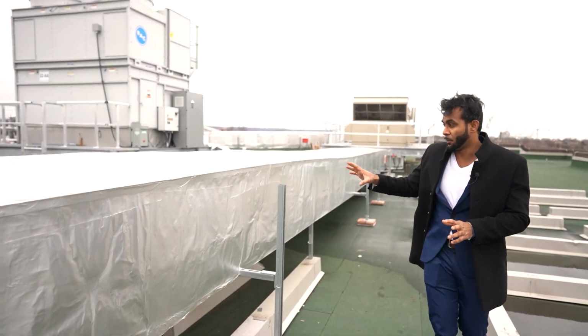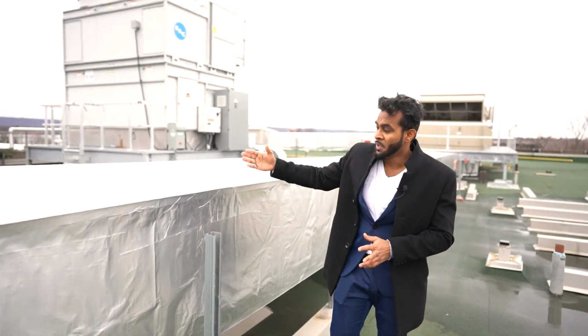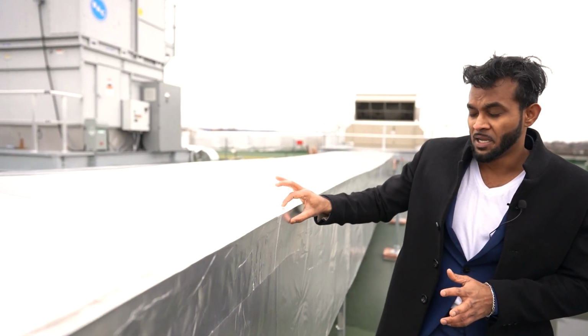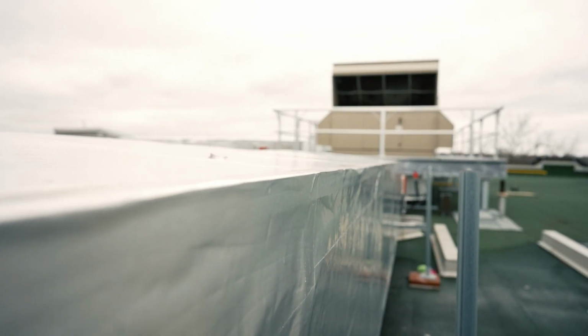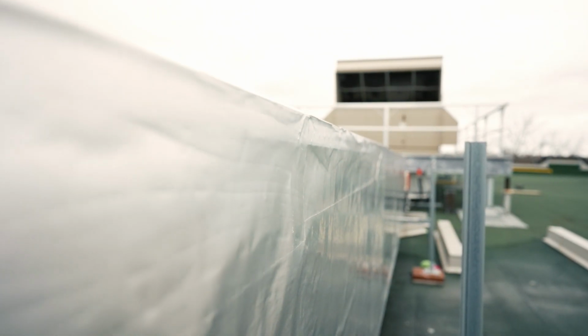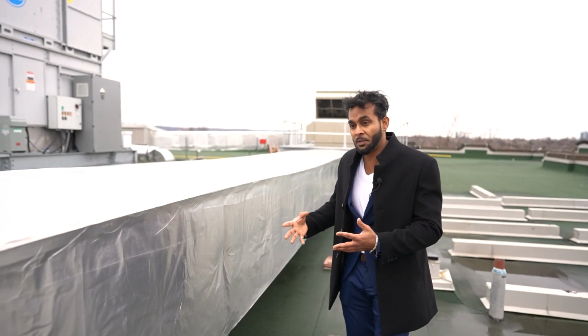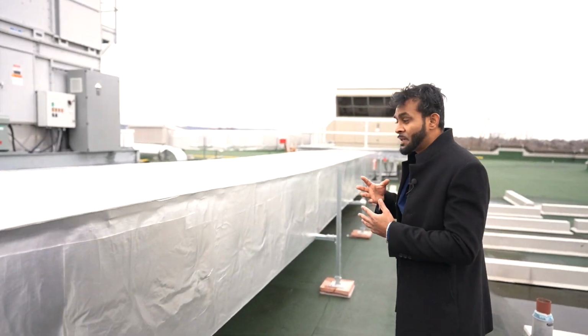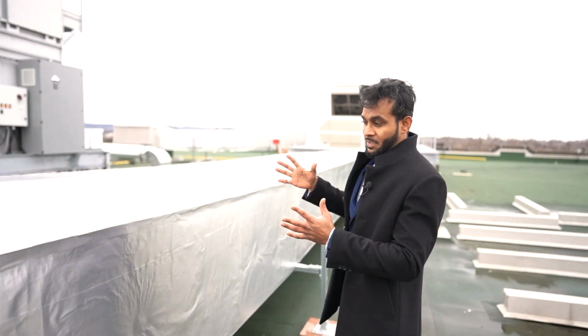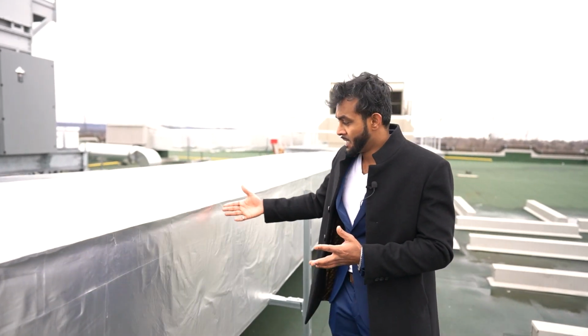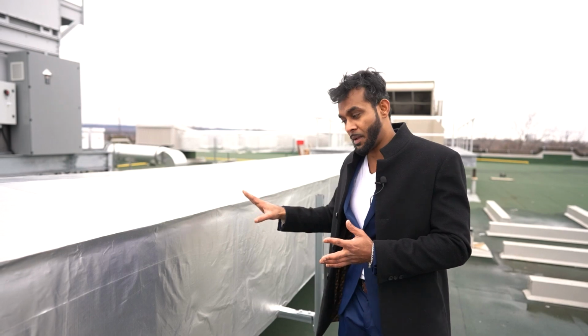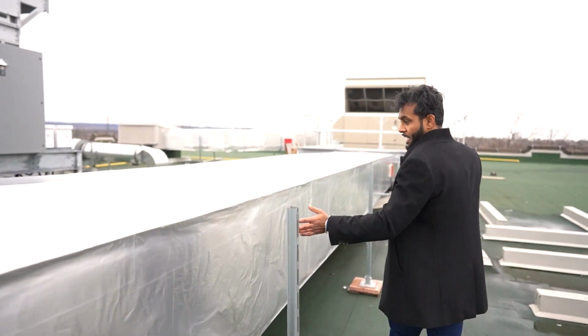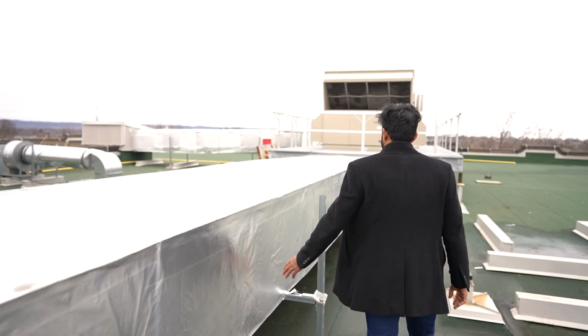As you can see, we've insulated this. How we were able to get this nice edge is we used drywall beads, the aluminum drywall beading, put it on the side, added the insulation, and then wrapped it with what's called aluminum jacketing. This is used for weatherproofing, to make sure that during our Canadian seasons, especially summer and winter, when everything contracts and expands, you have something reliable. That's why they always recommend an aluminum jacketing on top of the insulation.